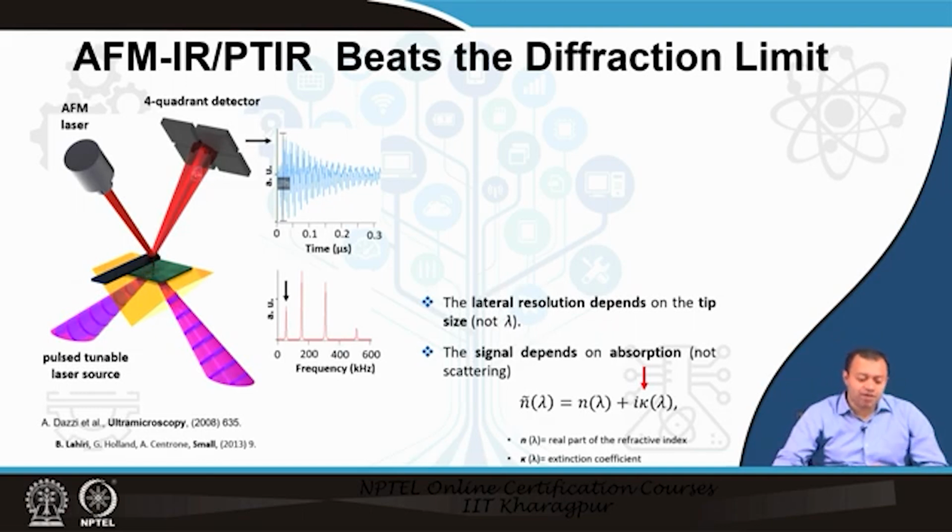It is connected with the feedback mechanism, the feedback loop, everything like any other atomic force microscope. Those of you who have used an atomic force microscope will understand it very quickly. Those of you who have not, do not worry, it is simple. Use that analogy of a pencil tip on top of a paper which is in contact with a coin below. So, this is the same thing. The cantilever is moving in x, y direction on top of a sample which is put on top of a substrate which is optically transparent.